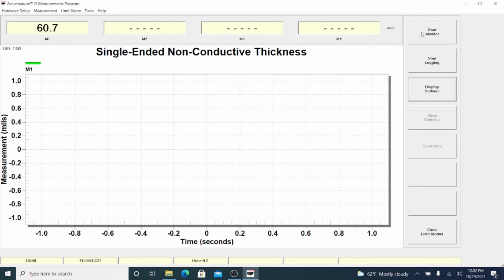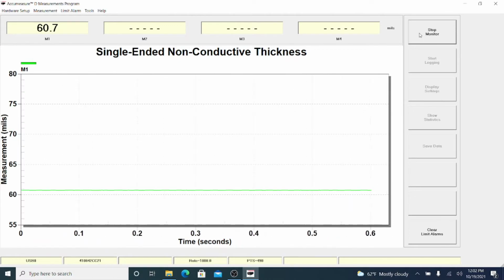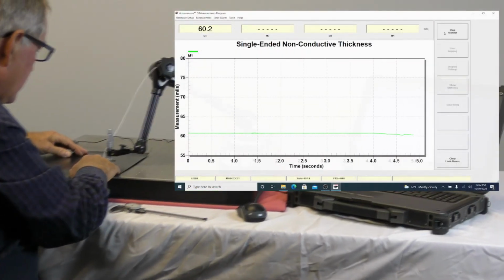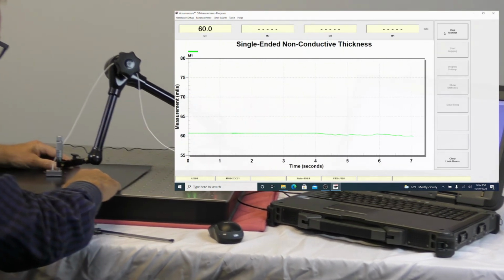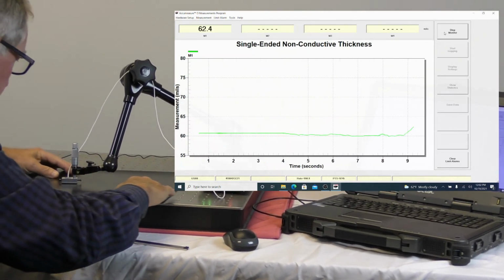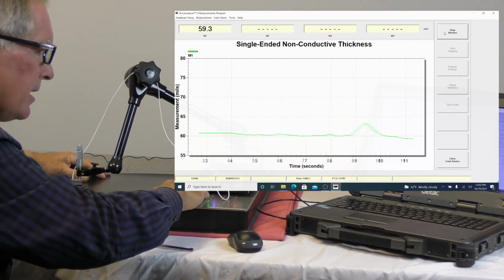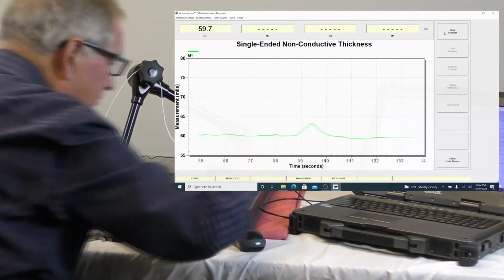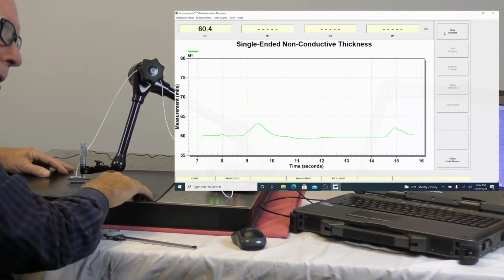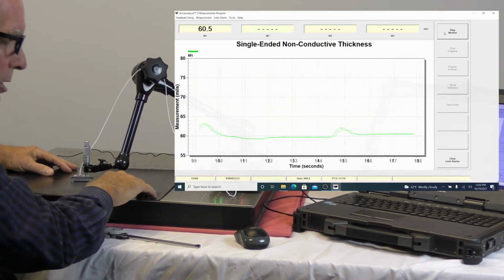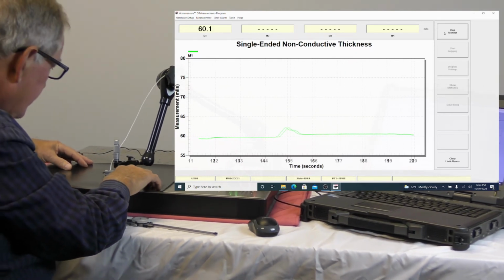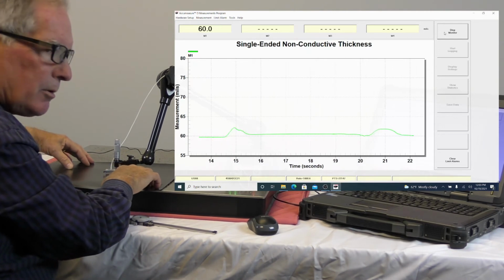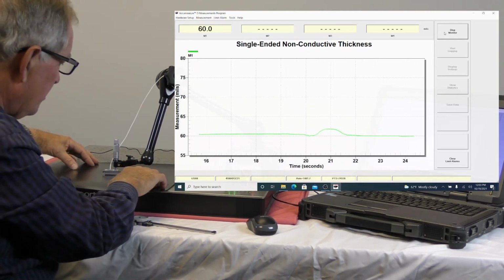So now if I hit start monitor, this is kind of like an oscilloscope display or a real-time monitor. As we start recording, you can see we have 61 thousandths of an inch showing there. And then I'm going to slide this sample across. Whoops, snagged it on my finger there. All right, and you can see where I snagged it on my finger and lifted it off. Now, you don't want your dielectric material to get too close to the probe face. As long as you're about a quarter of the distance away from the probe face, your readings will be good.